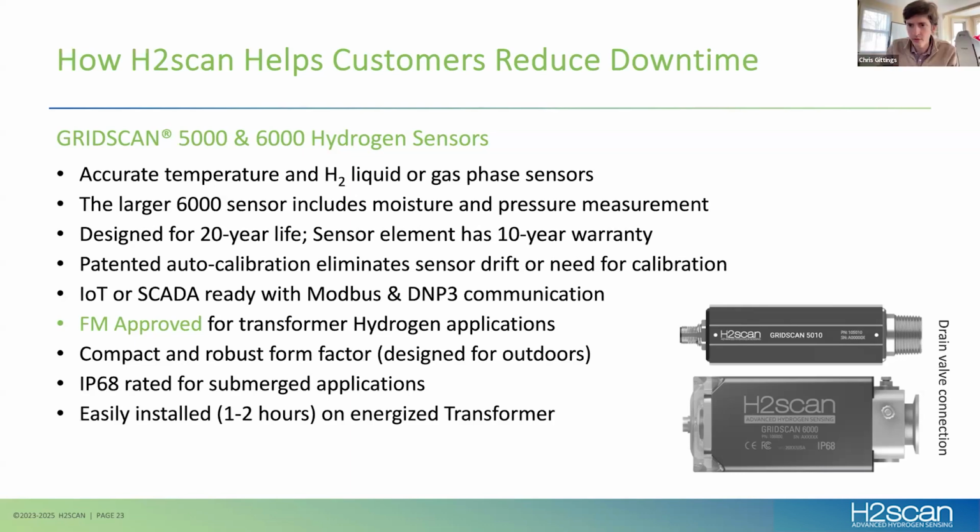What is the frequency of auto calibration, and how are you notified if it was not successful? Can you trigger a calibration? The frequency of auto calibration in the product you're looking at today is once every 12 hours. It is currently not designed to be triggered by the customer or an external party.